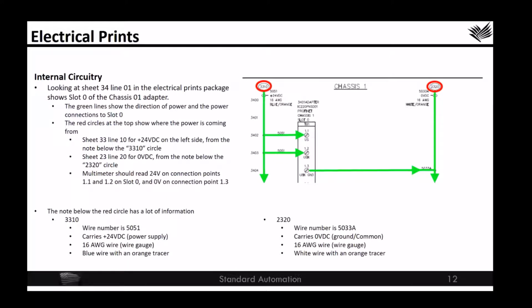Now, looking at sheet 34, line 01 in the electrical prints package shows slot 0 of the chassis 1 adapter. The green line shows the direction of power and the power connections to slot 0. There are two, one going into connection point 1.1 and another going into connection point 1.2 on the slot 0 card of chassis 1. The red circles on top of the green lines show where the power is coming from.